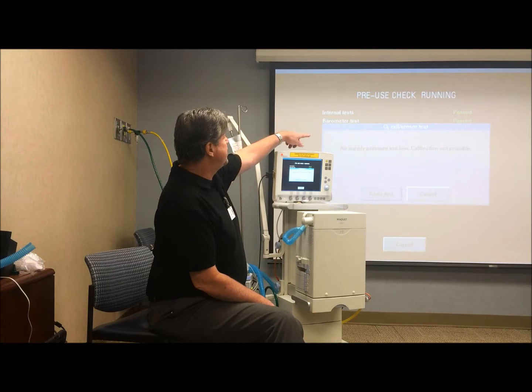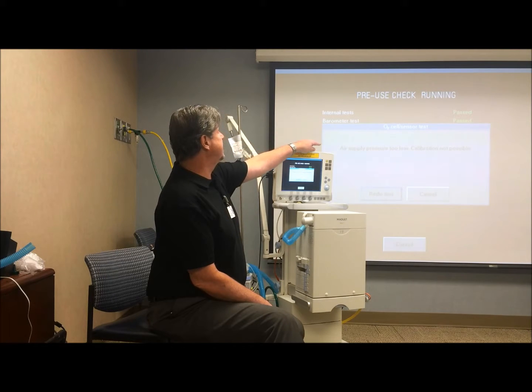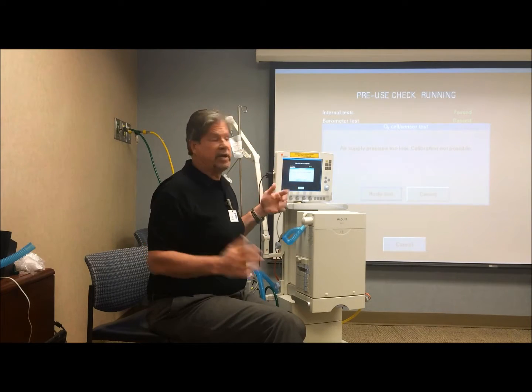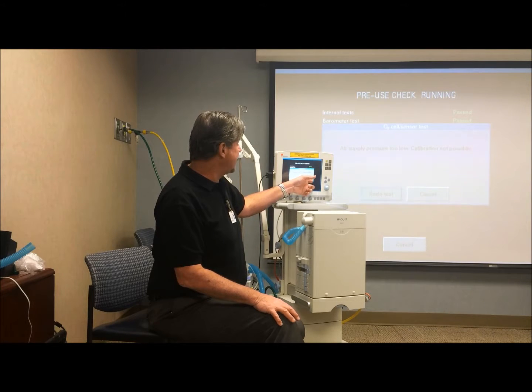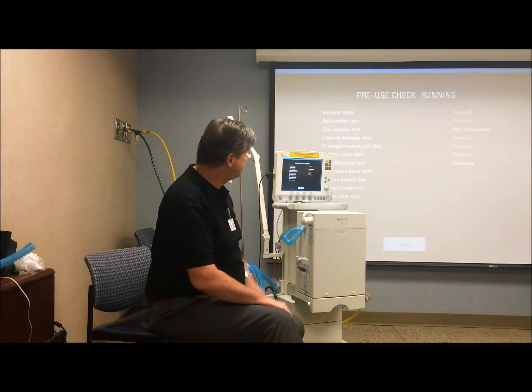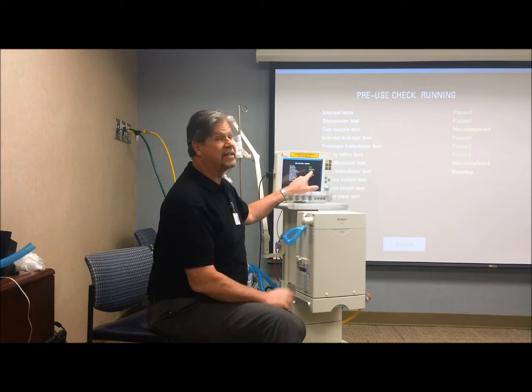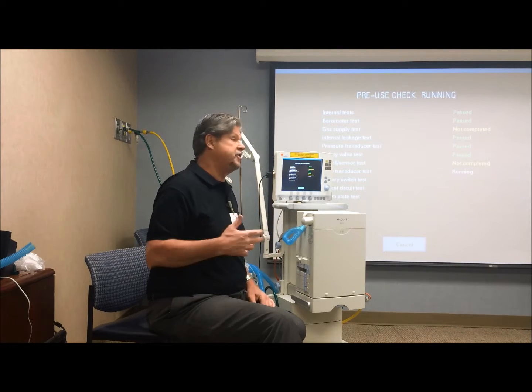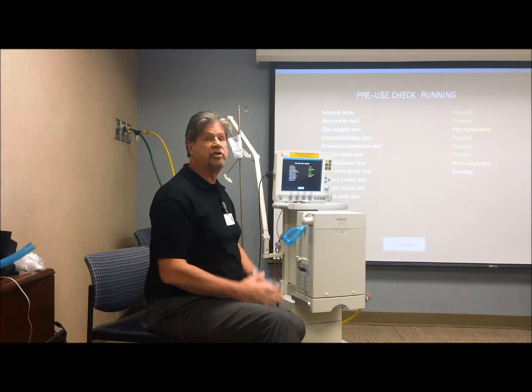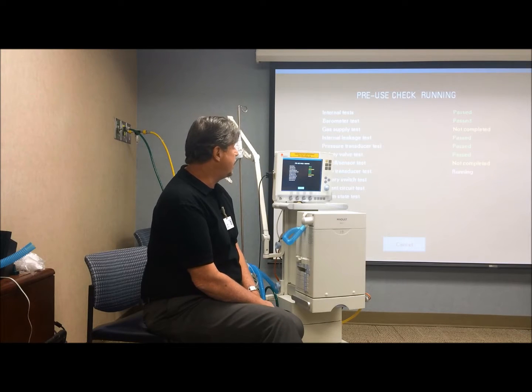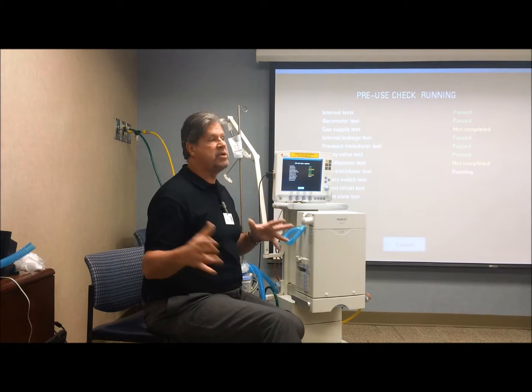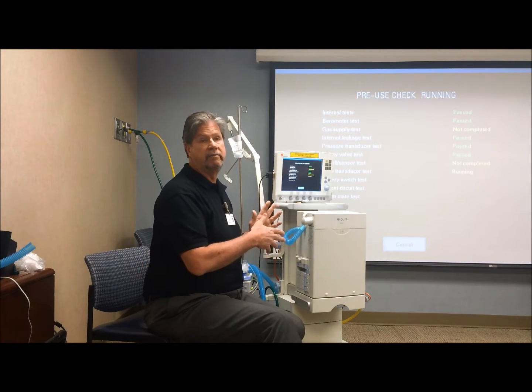So then it got to the O2 cell and sensor test, and it's air supplied, so it can't calibrate the O2. So we have to cancel that particular test, and once again, that says not completed. It doesn't say failed, it just says, I'm sorry, I couldn't do the test, so I can't complete it. Consequently, the whole pre-use check will be not completed.